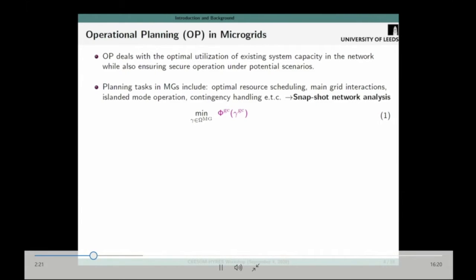In microgrid operational planning, the problem can be represented by two stages. In the first stage, we have a minimization of the costs for the grid connection operation. The cost function here, represented as phi GC, is dependent on gamma GC, which are the decision variables in grid connected mode. These usually involve the power exchange costs with the main grid, as well as the operational costs of the different generators in the microgrid.